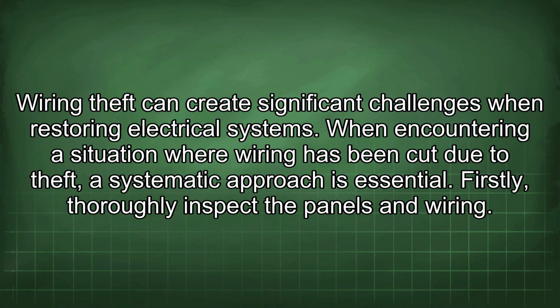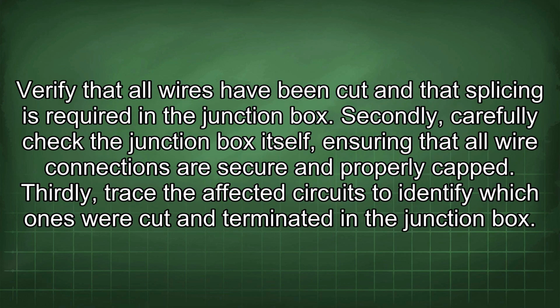Wiring theft can create significant challenges when restoring electrical systems. When encountering a situation where wiring has been cut due to theft, a systematic approach is essential. Firstly, thoroughly inspect the panels and wiring. Verify that all wires have been cut and that splicing is required in the junction box.